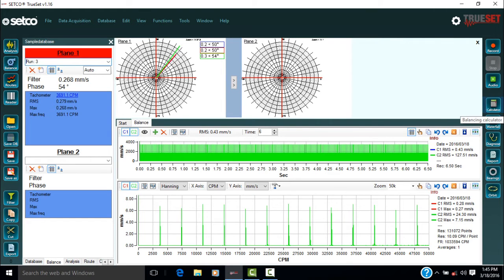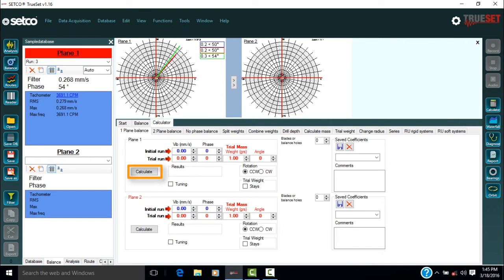Select the calculator icon. The first tab is One Plane Balance. This is used when balancing in one plane. Select one of the first runs under Initial Run. Select one of the runs with the trial weight under Trial Run. Enter the weight and angular position of the trial weight. Make sure the rotation is correct, as viewed from the front of the equipment.